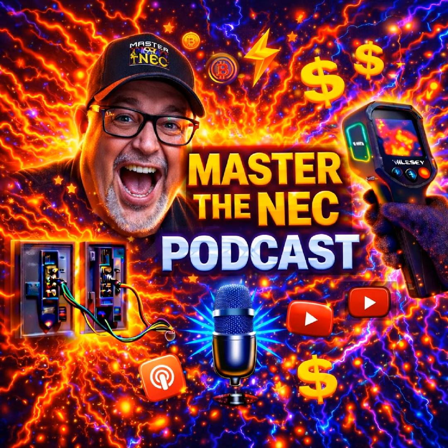And that's a problem. When we have storms around the country, people sell generators. People just go grab generators. They start hooking them up to systems. Electricians get involved. They don't understand these concepts, and they don't understand the difference between a bonded and an unbonded generator. They get confused. And that's a problem. Each system has to be evaluated on its own to determine what we actually need. You've got to look at the generator. You've got to look at the inlet. You've got to look at the cord. You've got to determine how you're going to transfer it. You've got to look at the neutral configuration. You have to understand the service bonding points, all of it. You've got to understand all of this.